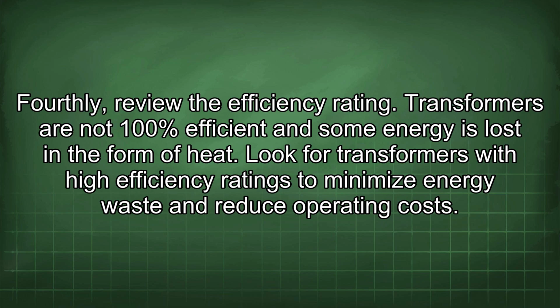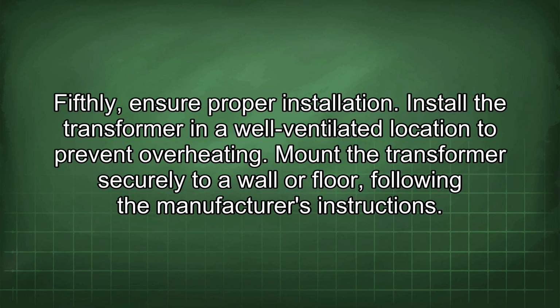Transformers are not 100% efficient, and some energy is lost in the form of heat. Look for transformers with high efficiency ratings to minimize energy waste and reduce operating costs. Fifthly, ensure proper installation. Install the transformer in a well-ventilated location to prevent overheating. Mount the transformer securely to a wall or floor, following the manufacturer's instructions.